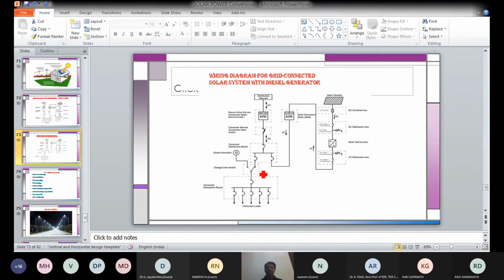What will happen: the remaining 0.5 kilowatt will try to enter into your diesel generator. Since grid is off, everything went fine, now diesel generator is there. If this 0.5 kilowatt enters into the diesel generator, again it will create a lot of issues. Again, one thing is there.